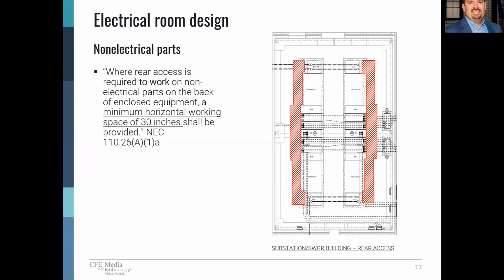The covers on the back can be either bolted on or doors, depending on the equipment. But the NEC in this case is really just setting the minimum criteria for rear access if the equipment requires it. It's best, however, that we check the manufacturer recommendation or requirements for the equipment and provide the requirements per the manufacturer for the specific equipment.